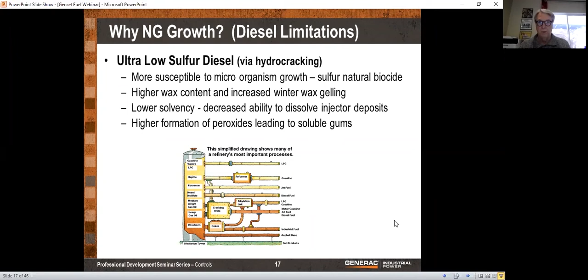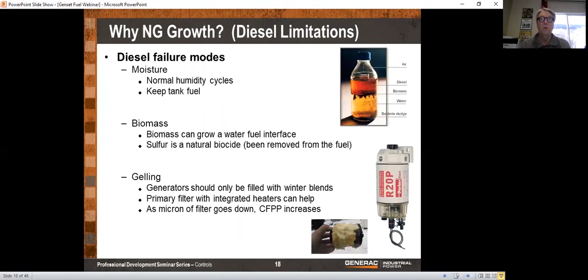So moisture is one of the problems. Biomass, we talked about, is much more common with low sulfur diesel fuels. And gelling: things gel in the winter in cold atmospheres. It doesn't make any sense to try to heat the tank. That's crazy. I've seen a lot of people like to do that, but I've never seen one actually do it. And so we simply have to use a winter fuel blend and put in anti-gelling compounds to make sure that diesel fuel doesn't gel at the lowest temperature which you expect to see during the winter.